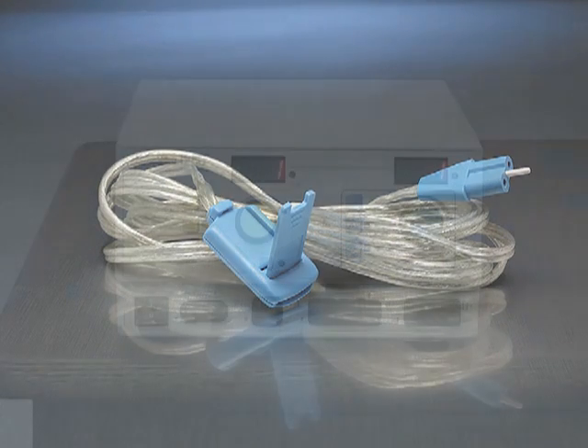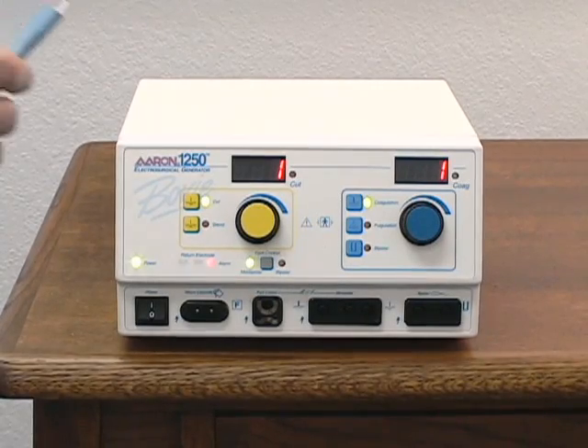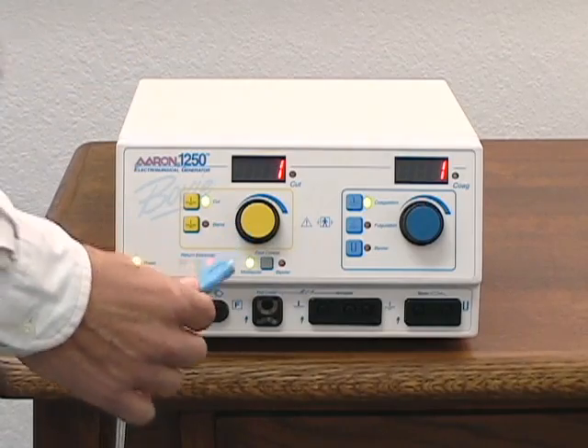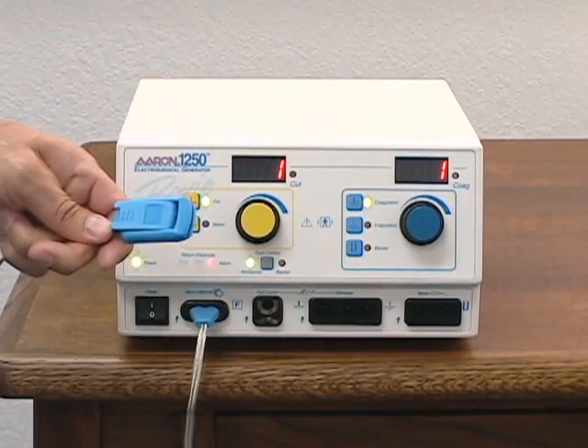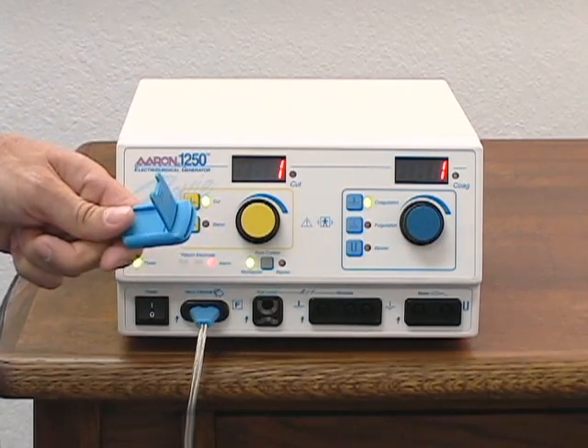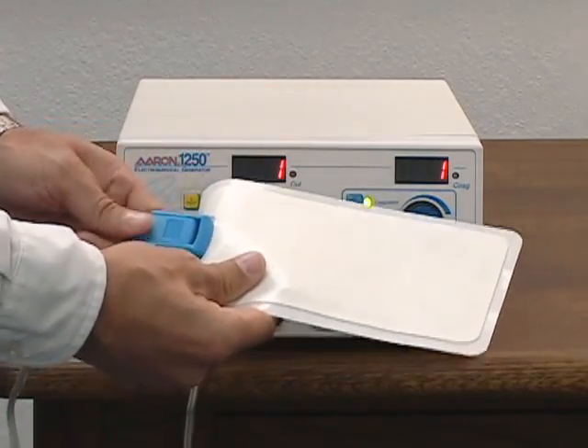The Aaron 1250 is packaged with a reusable grounding cable and five disposable split pads. To install the cable, insert the plug into the receptacle marked return electrode. To attach the pad to the cable, open the locking mechanism, insert the tab into the clip, and close the locking mechanism.